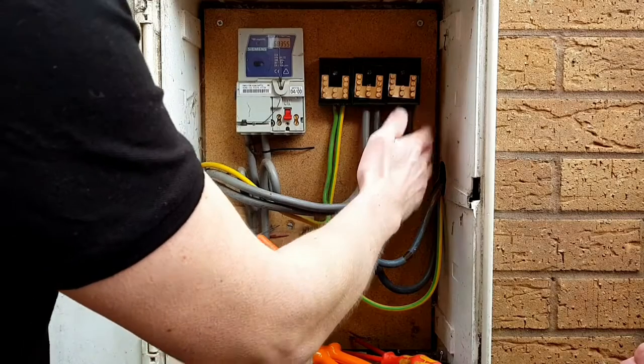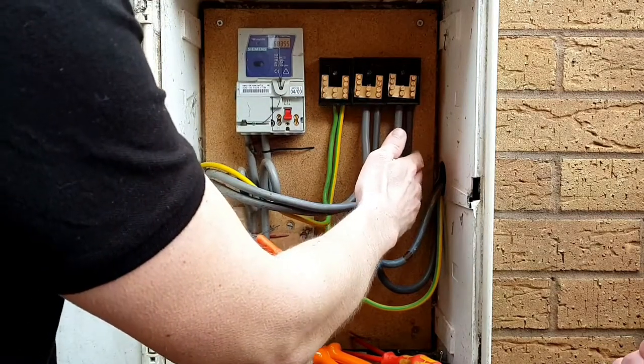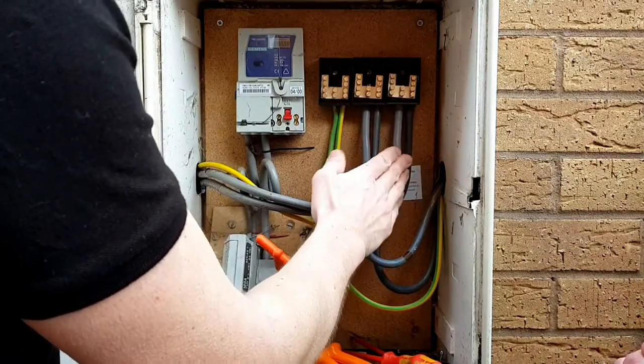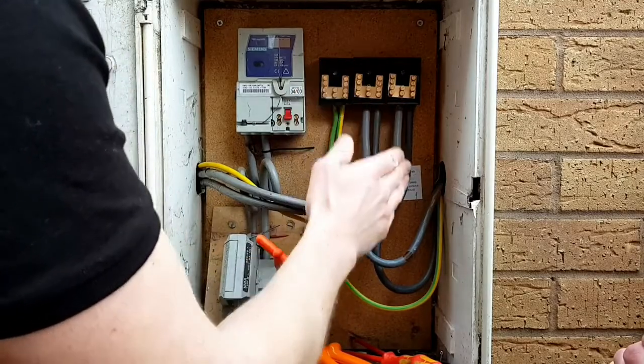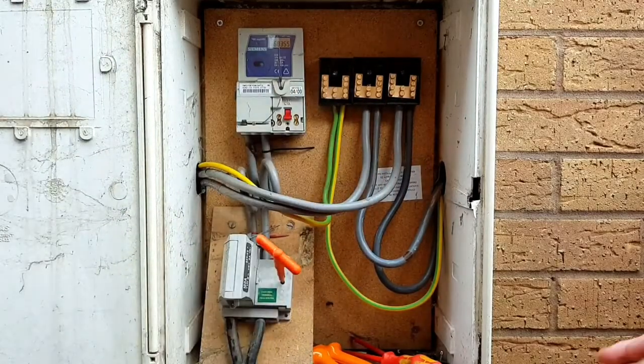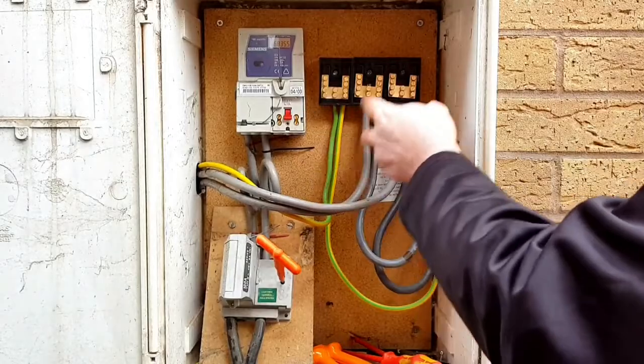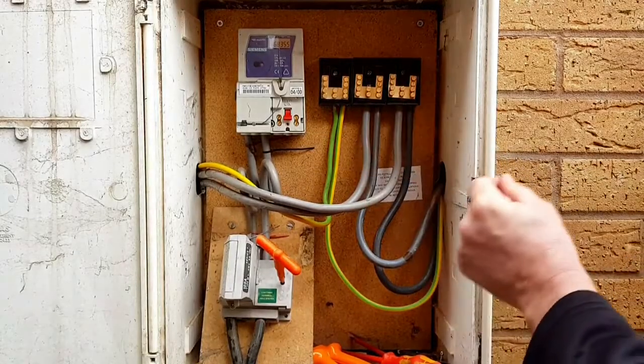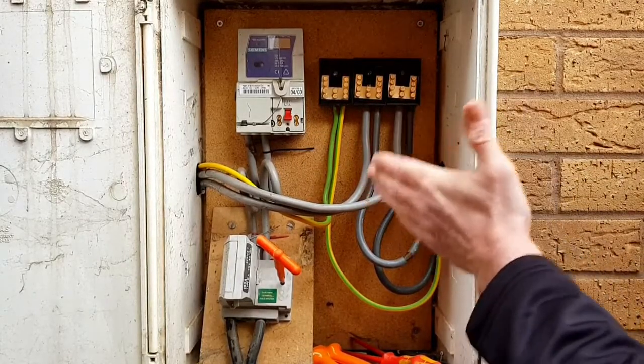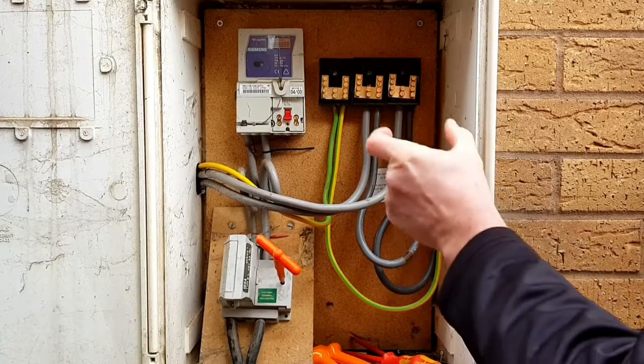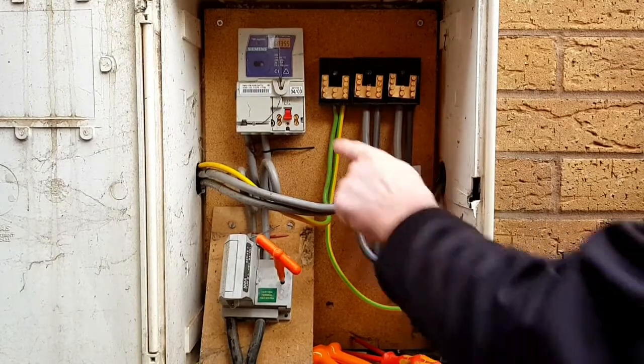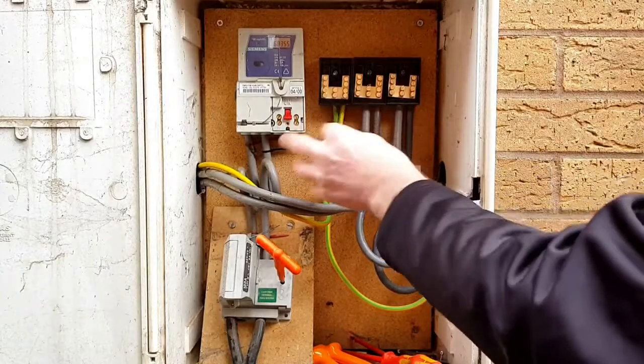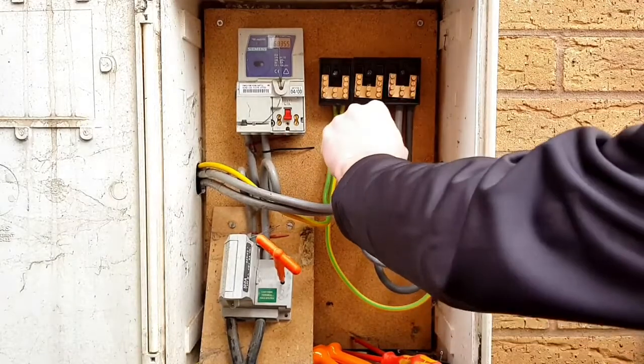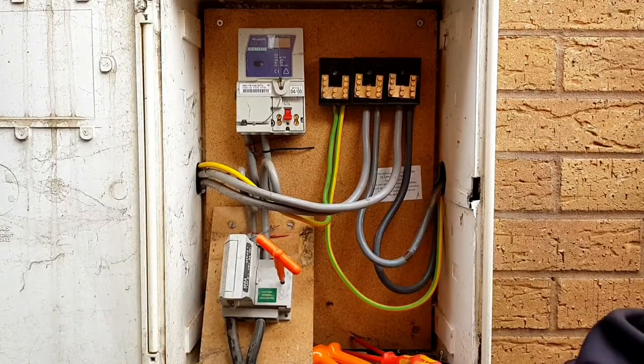So we've got our new tails going off to our new consumer unit here. We've got our existing tails going off to our existing consumer unit on this side, and all that remains now is what? We're going to actually put the neutral and line conductor into these blocks to energize them, and it's important that we leave enough on the line conductor in order that we can put our CT onto it. So it's no point having a really tiny one or a tight bend and find that you can't actually put on the CT over the top of it. So it's important that we do that next.